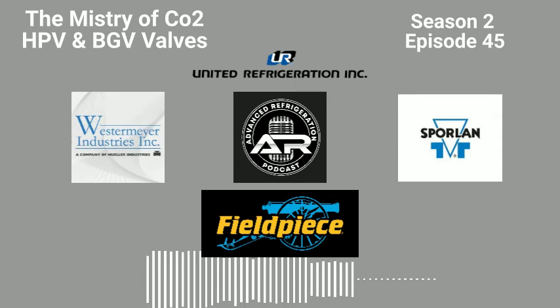So one of the things I've noticed is, unfortunately, with all the extra stuff that you have to do, there's a lot of extra control. And that's why dealing with and getting these racks tuned, with these 2 valves, is kind of a bitch, because there's so many different set points. You have to tell it when it's technically transcritical. You have to tell it what your subcooling is when you're running in subcritical mode, and then you have to tell it what it's going to run when it's in transcritical mode. So there's so many set points, not just for the HPV, but for the BGV as well.